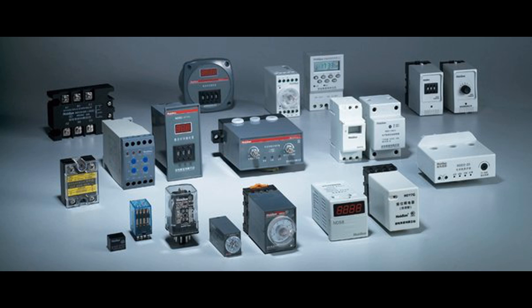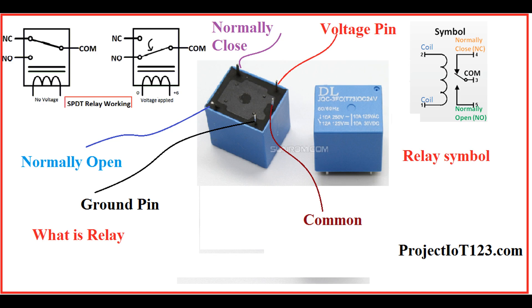Control Signal Application: When the control signal is applied to the relay, instead of an immediate response, the relay enters the delay period. The contacts will only change their state after the specified delay time has elapsed. Control Signal Removal: In relays with delay on release, when the control signal is removed, the relay enters a delay period before the contacts return to their original state. This delay can be crucial in preventing rapid and undesired state changes.